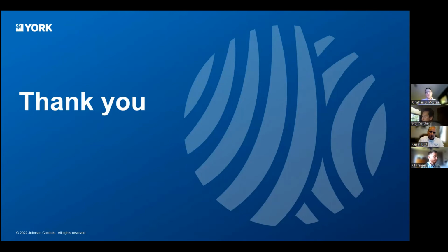Terrific. What is the range of CO2 emissions in metric tons that can be avoided per year through the use of these type of heat pumps? Excellent question. It really depends on the baseline, and whether we are talking about shifting away from coal and natural gas fired legacy systems. But if I were to assume a very broad range, I would say anywhere from 2,000 metric tons of CO2 avoided per year to something like 10,000 metric tons of CO2 avoided per year. It could be a little bit smaller, it could be larger, but at least it gives you some range.